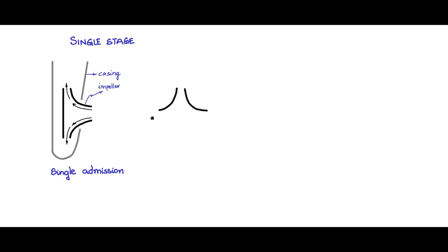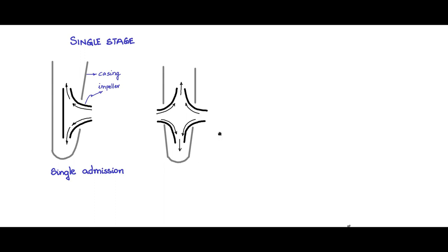You also have double admission — the impellers look like this, and water can be admitted from both sides. Water comes out because of the pressure difference between the center and the outer periphery — centrifugal force pushes it out. Double admission is more advantageous because water admitted through both ports balances the impeller wheel, reducing impact on the bearings.